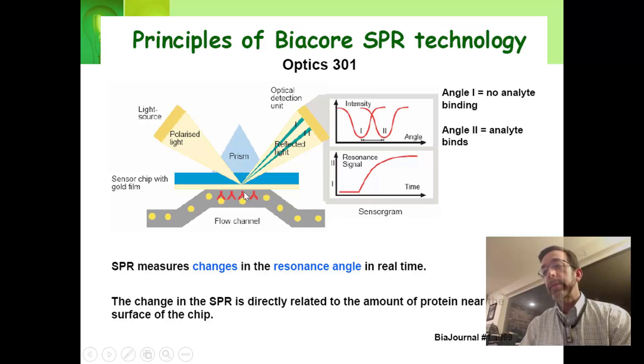The flow channel is moving the liquid through, and you can have something attached to the surface — these little red upside-down Ys attached to the surface. If it sticks to the yellow thing that you're flowing through the flow channel, then you'll have something approaching the surface. It changes the refractive index. When the refractive index changes, the angle of reflected light will also change. The shadow will also change, and you have an angle shift from 1 to 2, interpreted as a resonance signal — a response unit that goes up.